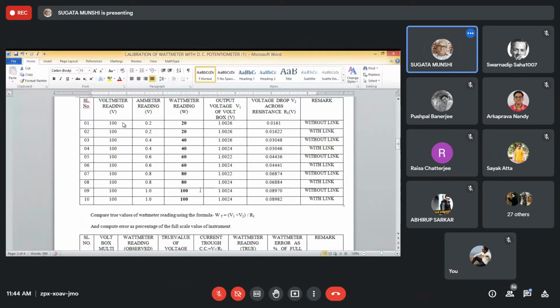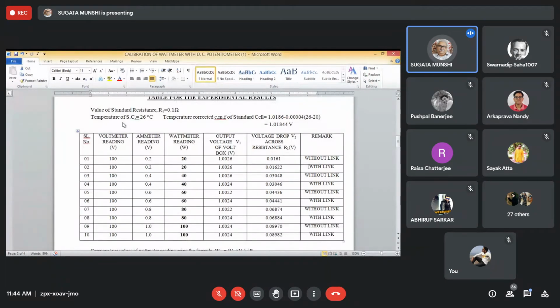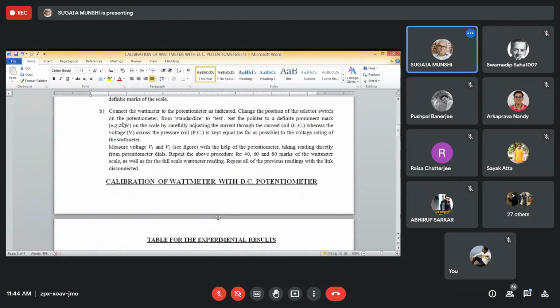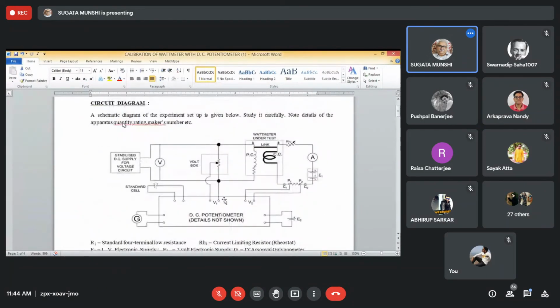Now, there are two types of readings considered here: with link and without link. With link means we have shorted the plus-minus marked terminals of the potential coil and current coil circuit, and carried out measurement under that condition. We will take another measurement with this link disconnected.